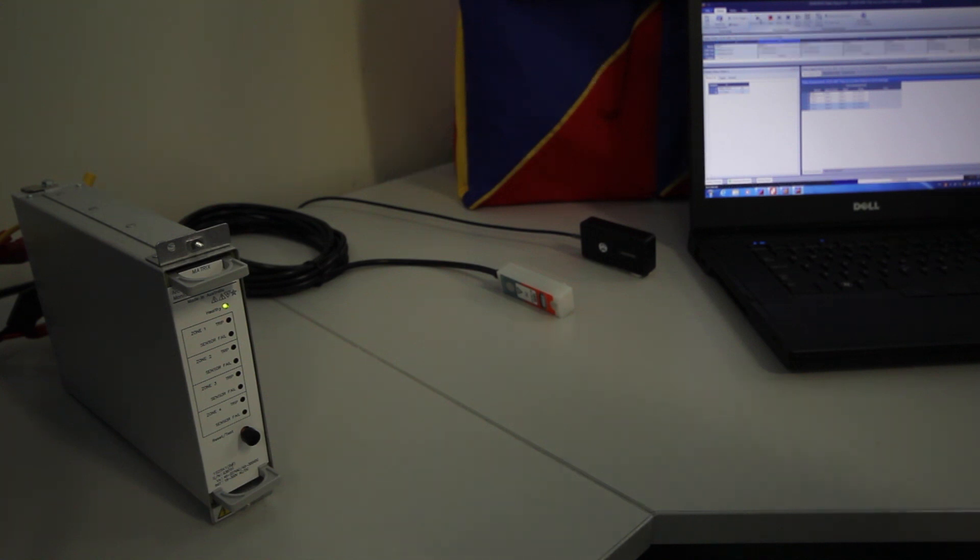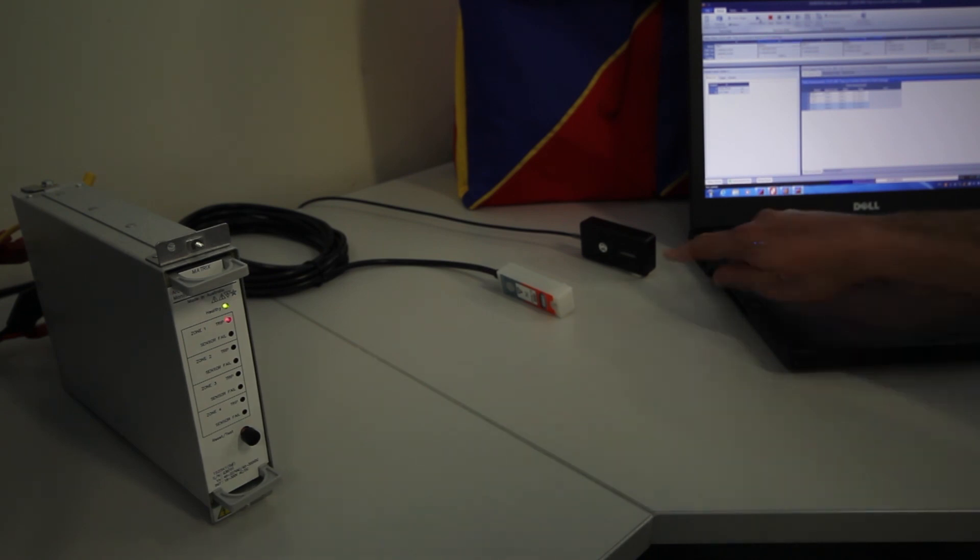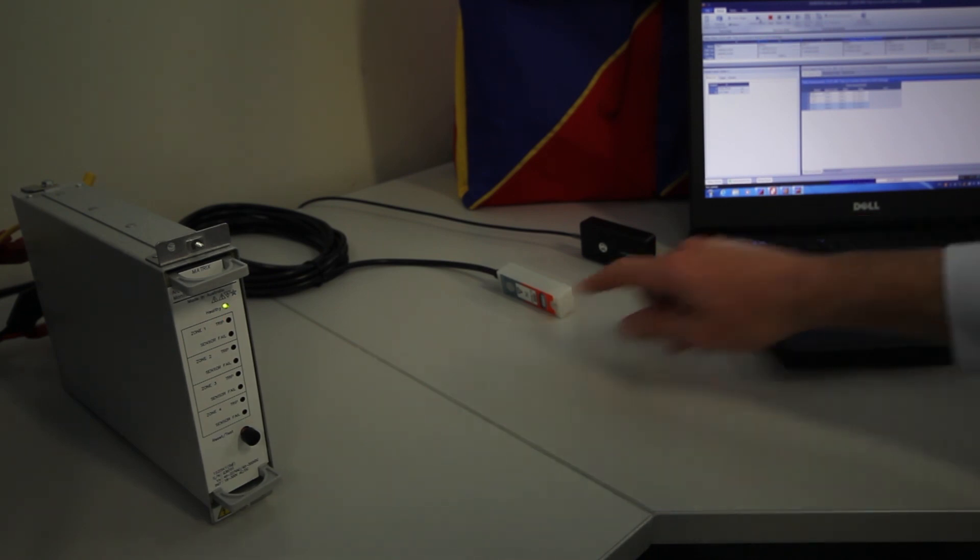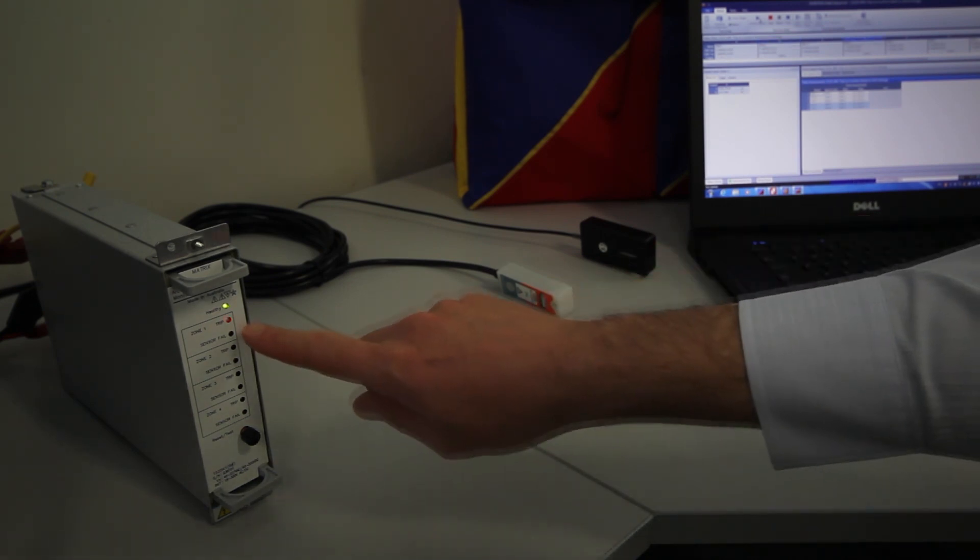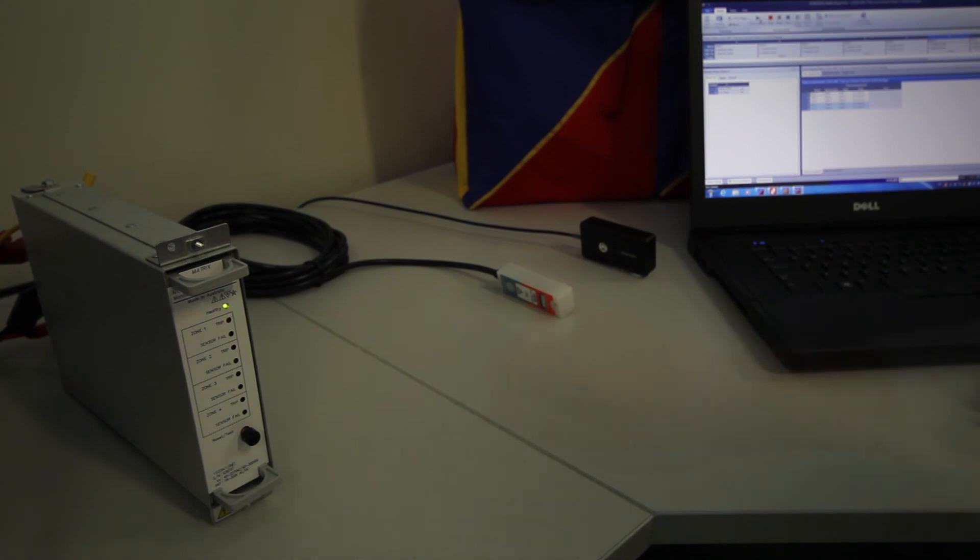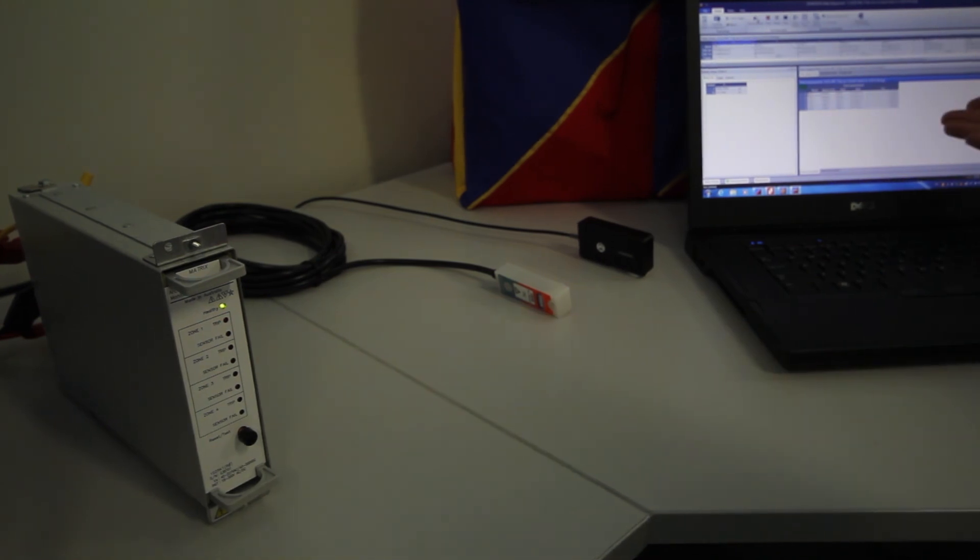What you can see is the arc flash being picked up by the 1S25 and annunciating the zone of operation, in this case zone 1.